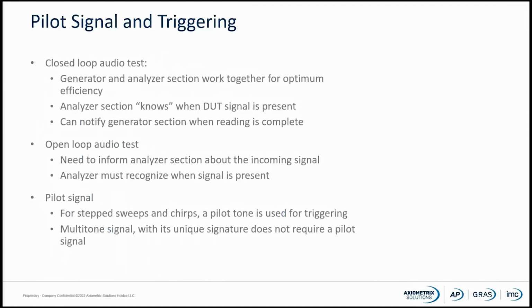In a closed loop test, the generator and the analyzer work together, informing each other of starting a measurement, moving to the next measurement step, and when the measurement is completed. When making open loop sweep measurements, we use a pilot tone just before the stimulus signal to trigger the start of the measurement. The pilot tone is usually a 1 kilohertz signal.